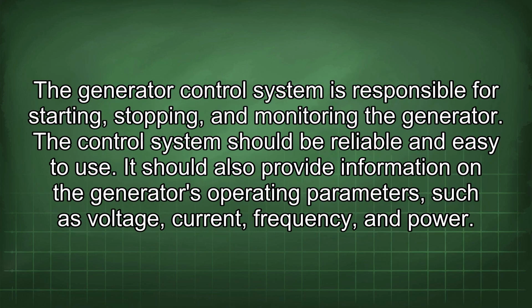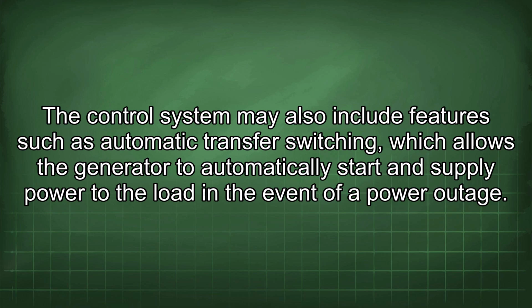The generator control system is responsible for starting, stopping, and monitoring the generator. The control system should be reliable and easy to use. It should also provide information on the generator's operating parameters such as voltage, current, frequency, and power. The control system may also include features such as automatic transfer switching, which allows the generator to automatically start and supply power to the load in the event of a power outage.